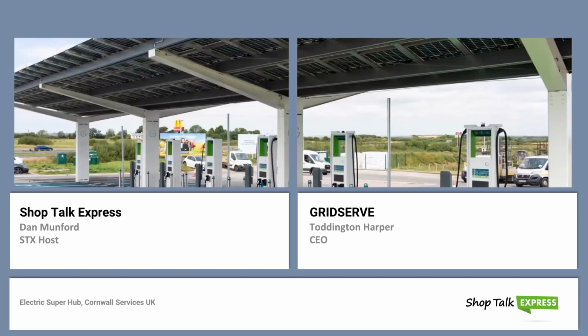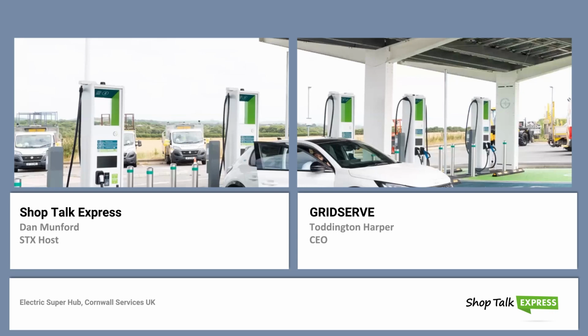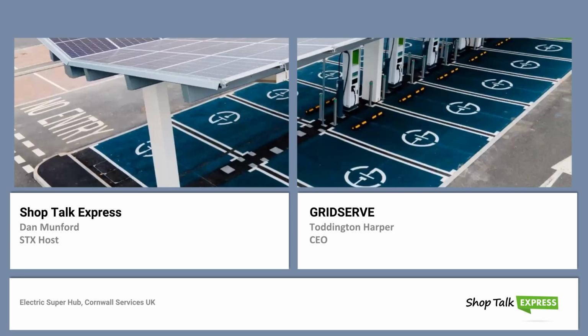We also have dynamic power control, so we're pushing power onto different chargers as well, which provides a great experience. You don't have to assign it to one charger in particular, which again is really helpful from a customer perspective, because vehicles aren't all charging at the same time. And we also have controls that if we think that we're going to run out of energy, we can slow things down, so we can share the energy more evenly. It's a constant process of learning, and we're getting better at predicting. What we also have on this canopy is a solar canopy on top of it, which is great, particularly in Cornwall, particularly in the summer where it's very busy.